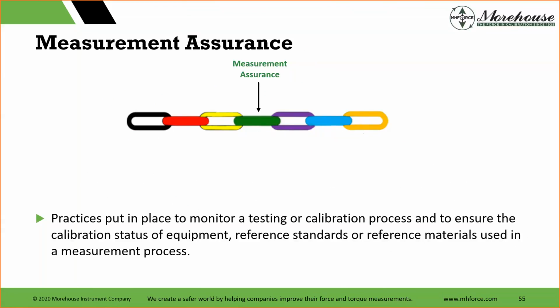This is SPC, statistical process control. This is maybe sending a check standard, a check force, a check torque standard, to a company. They do the cal. Now I use that check standard to monitor my process. I know what the answer should be. They told me what it should be. I tweak my setup, and then I continually keep testing that machine with statistical process controls in place. That way I can see if things are drifting out.